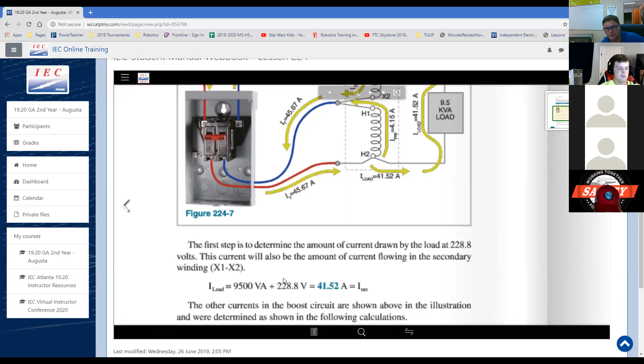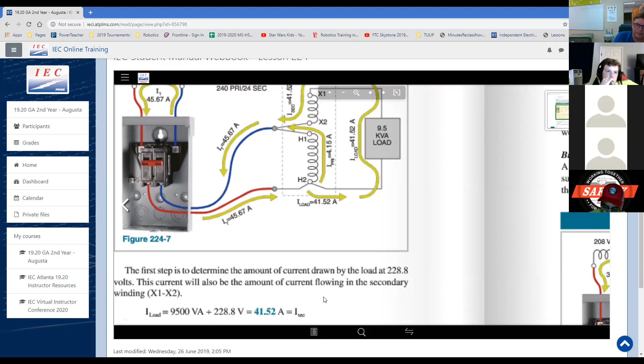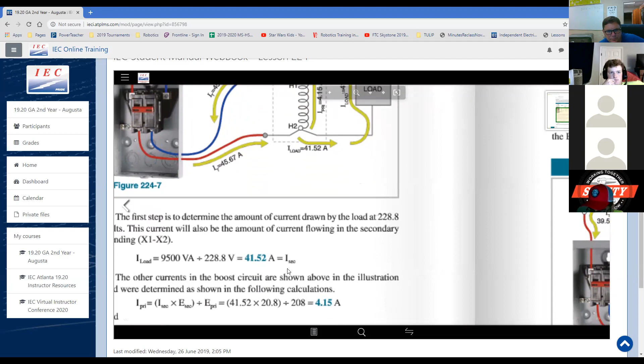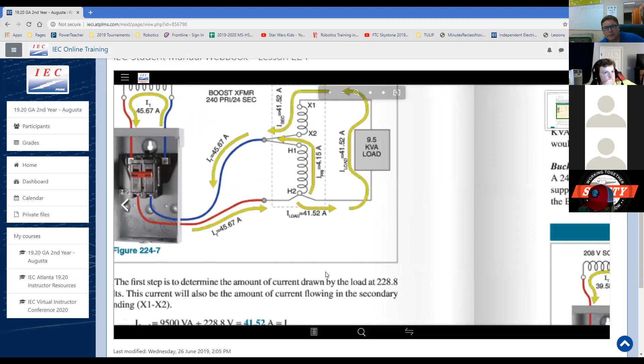So that's 9,500 VA, or 9.5 kVA, divided by 228.8 volts, which is what we have with our buck boost. We end up with 41.52 amps. So now we know the current through the secondary. But what about the other currents - where's this 4.15 coming from? Let's find it.